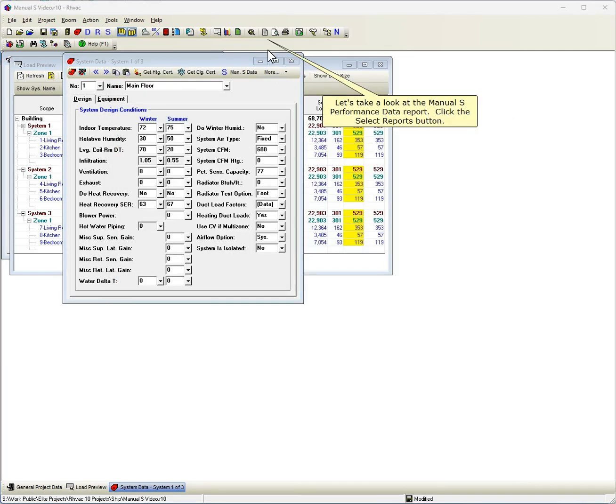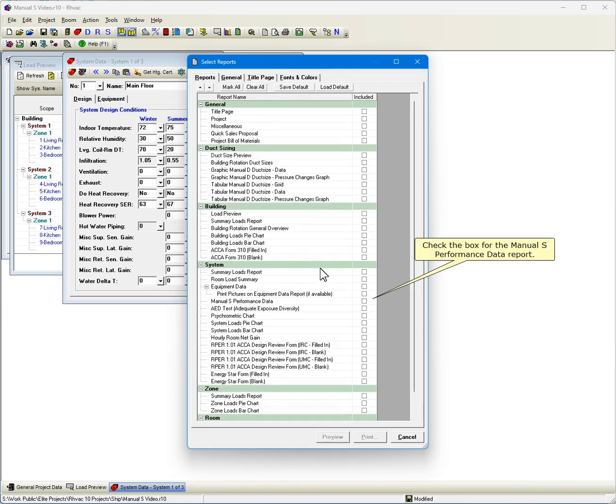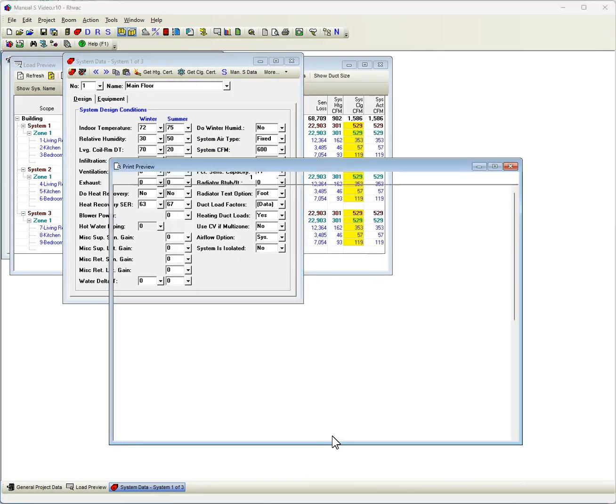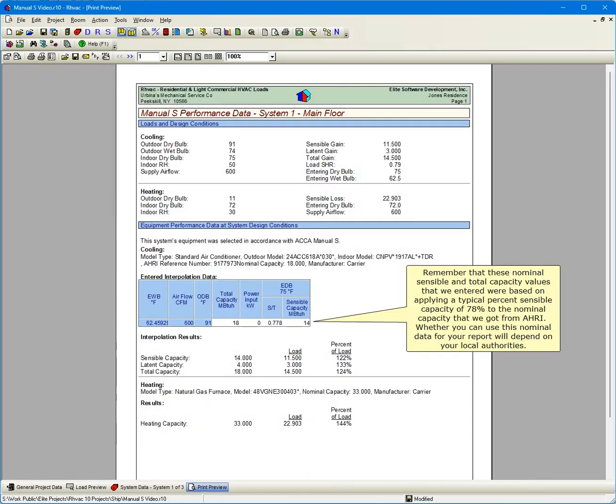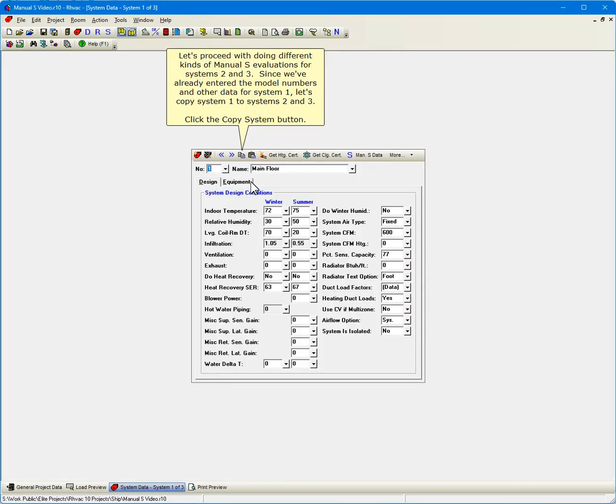Let's take a look at the Manual S Performance Data Report. Click the Select Reports button. Click Clear All to uncheck all the reports. Check the box for the Manual S Performance Data Report. Click Preview. Remember that these nominal, sensible, and total capacity values that we entered were based on applying a typical percent sensible capacity of 78% to the nominal capacity that we got from AHRI. Whether you can use this nominal data for your report will depend on your local authorities. Let's proceed with doing different kinds of Manual S evaluations for Systems 2 and 3. Since we've already entered the model numbers and other data for System 1, let's copy System 1 to Systems 2 and 3.